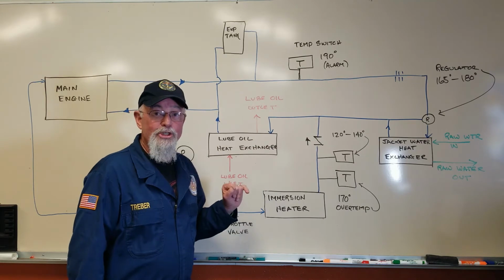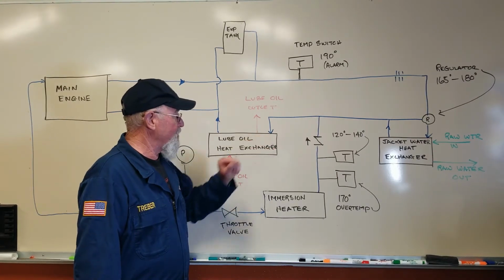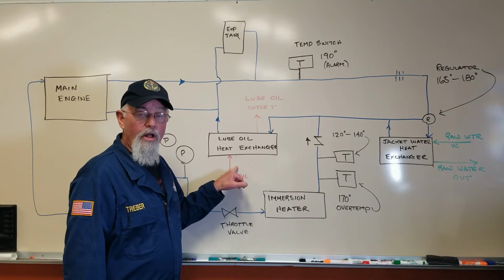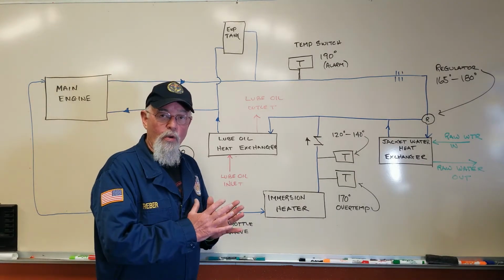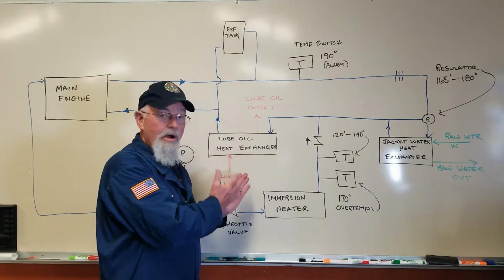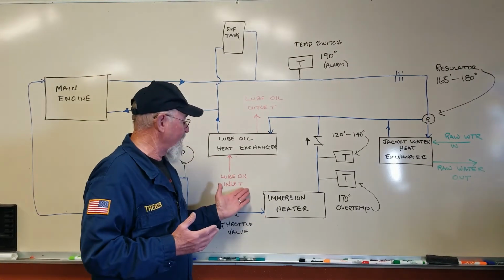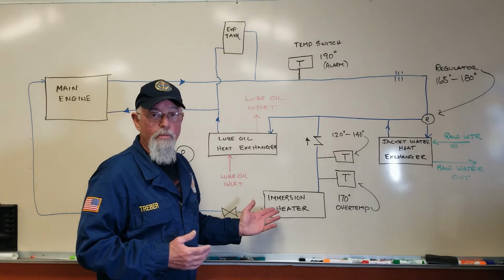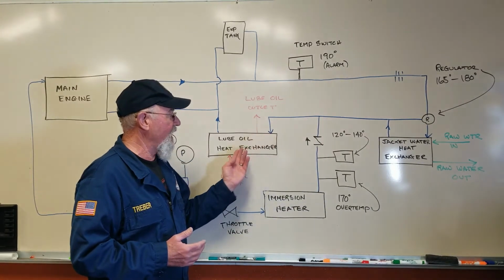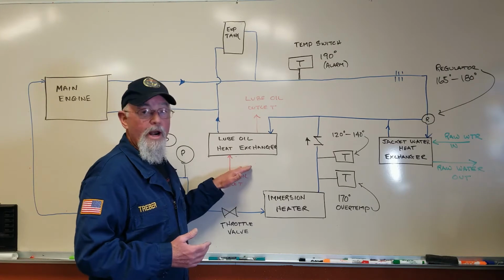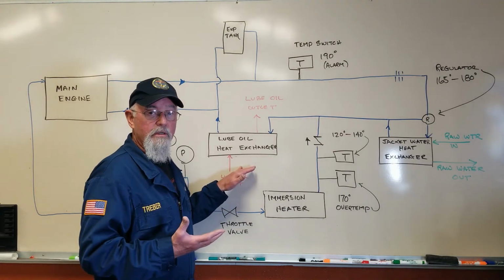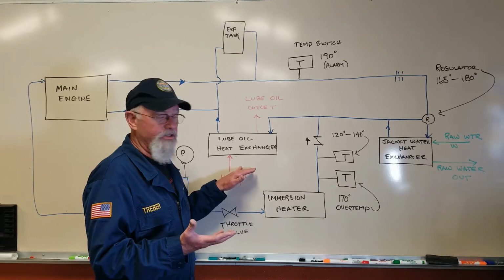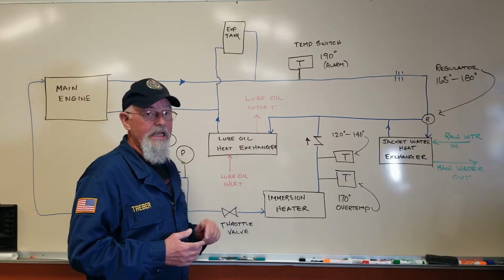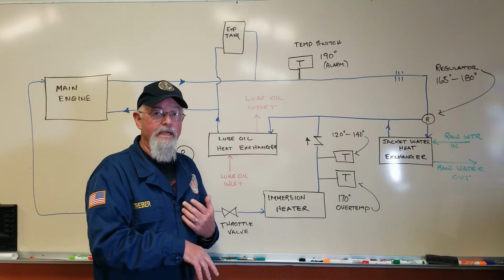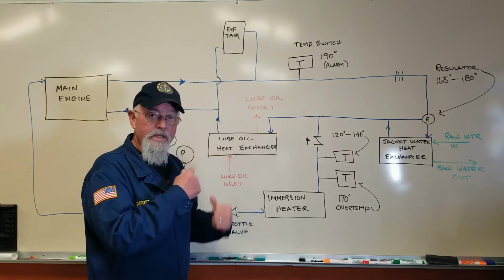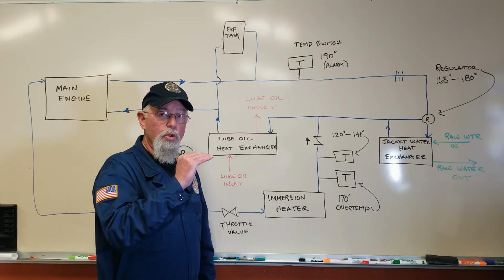So if there's a temperature differential between the temperature of the jacket water and the temperature of the lube oil, well, heat transfer goes from hot to cold. So assuming when you set this system up and you energize it, the lube oil temp's cool and the jacket water temp's cool, but as that temperature increases, you're going to start getting heat transfer. So we're warming up the contents of the sump as far as the oil gallons are concerned. Every time that lube oil goes through the heat exchanger, it picks up a little bit of heat, dumps it back into the sump, picks it back up again. So every time it cycles through there, the temperature is slowly increasing.